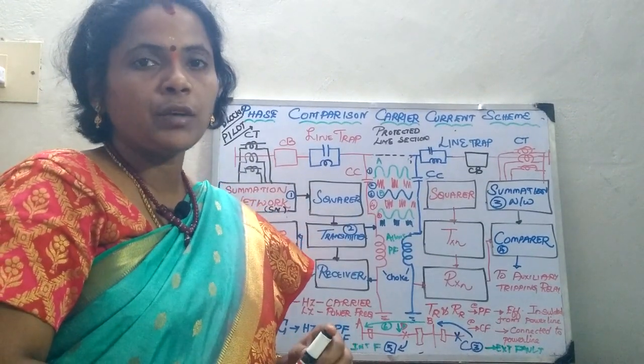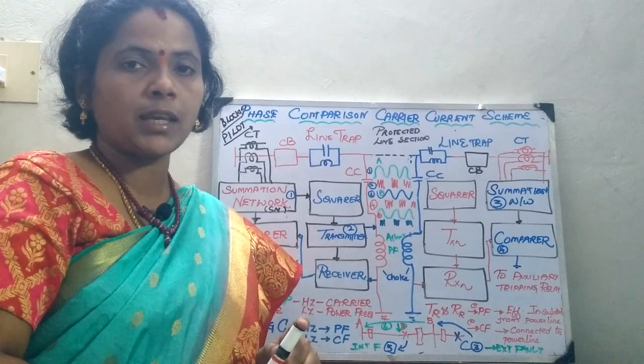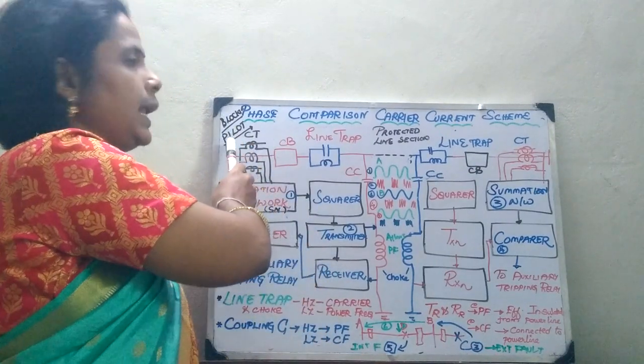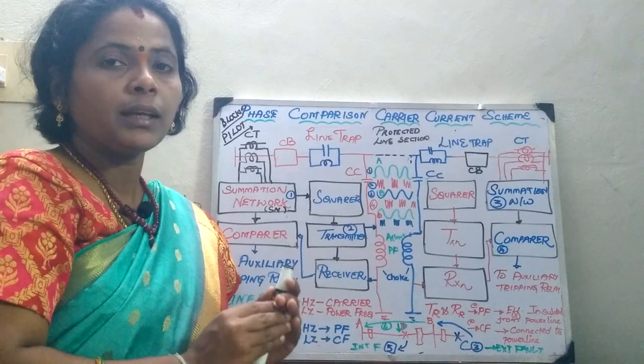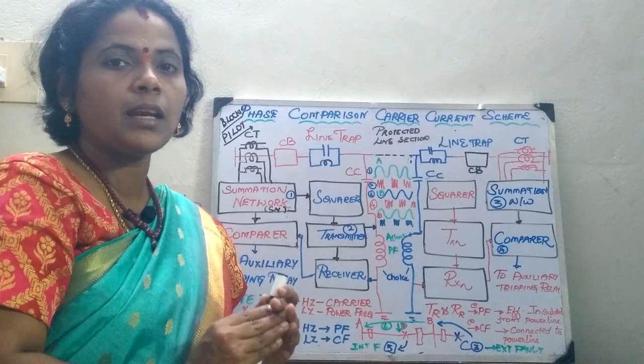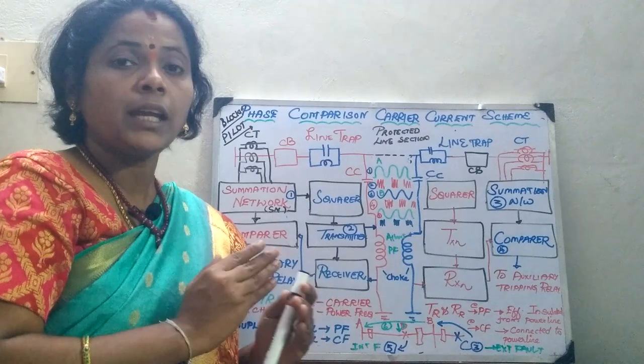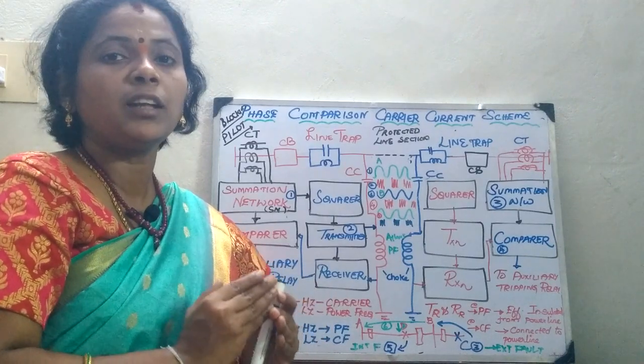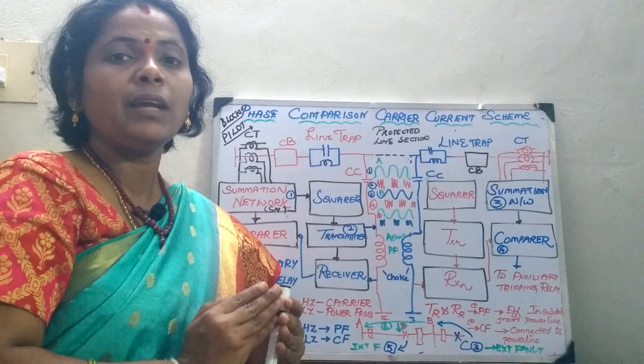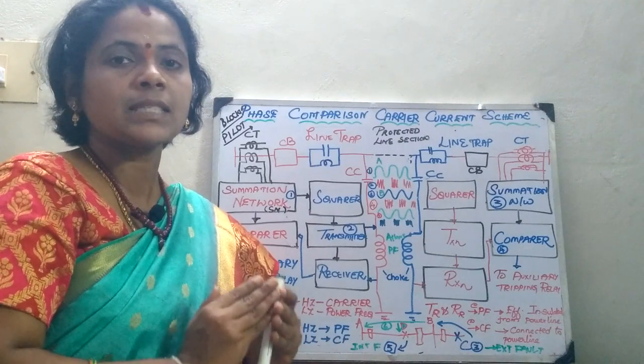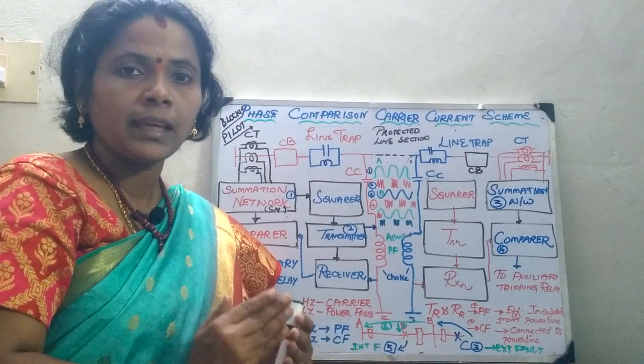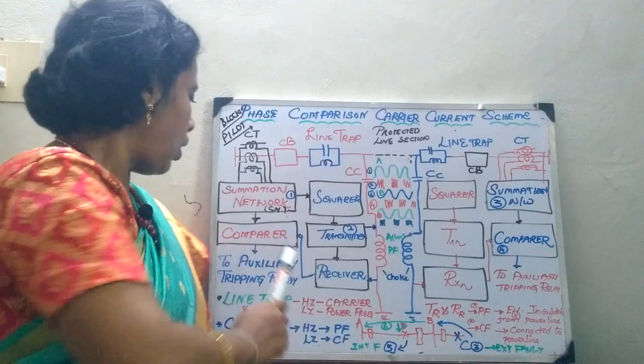We have seen that the phase comparison scheme acts as a blocking pilot. That means if the carrier signal is present, it is going to prevent the tripping of the relay. Only when the carrier signal is not there will the relay operate.